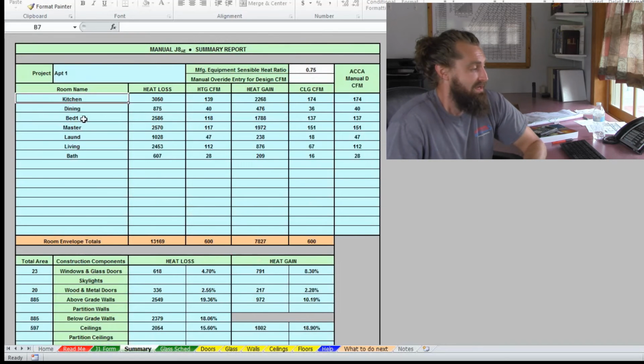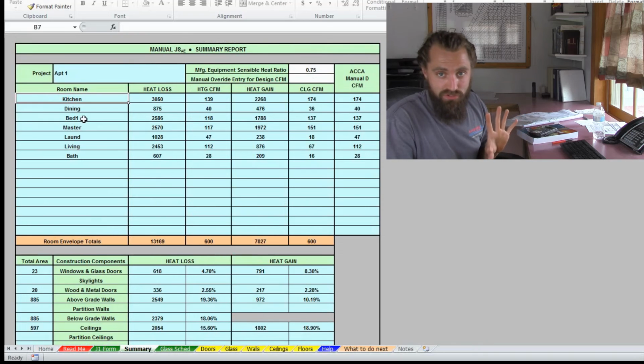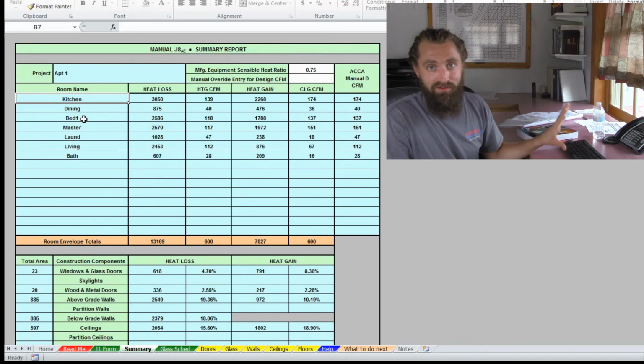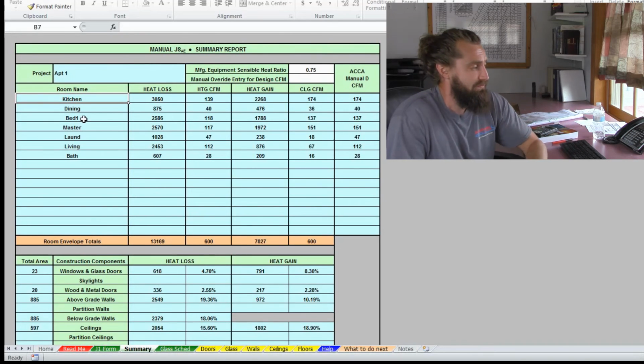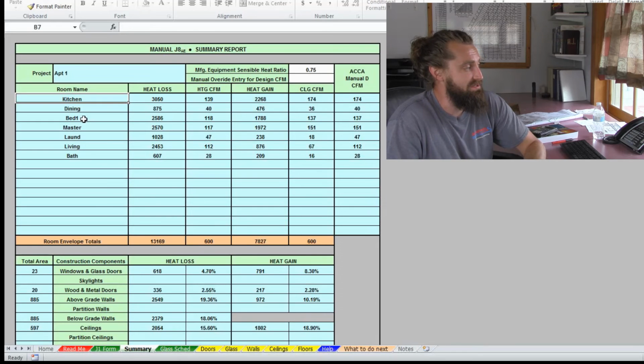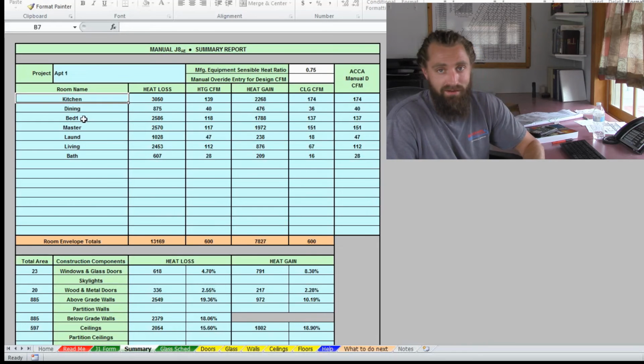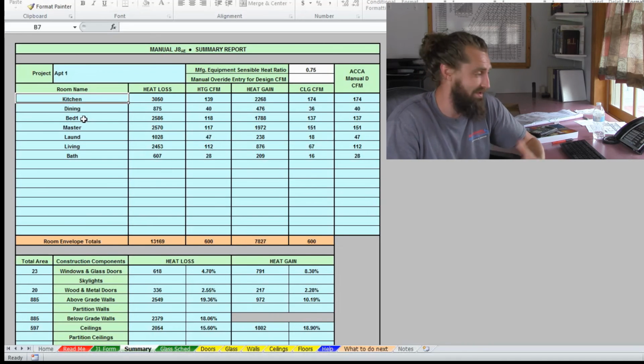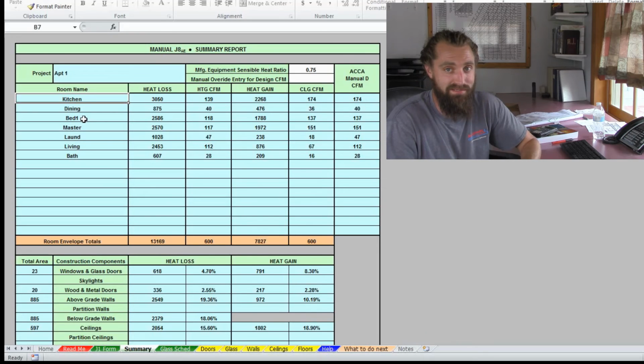Now, we're just walking through the example of that apartment. To do this all, I don't think I would use these numbers here per se. This gets you a pretty close ballpark when we're looking at a specific building. But would I use these exact numbers? I don't know. The biggest problem is we're not going to be able to do a Manual S and find a piece of equipment that gives us exactly 7,800 BTU cooling.